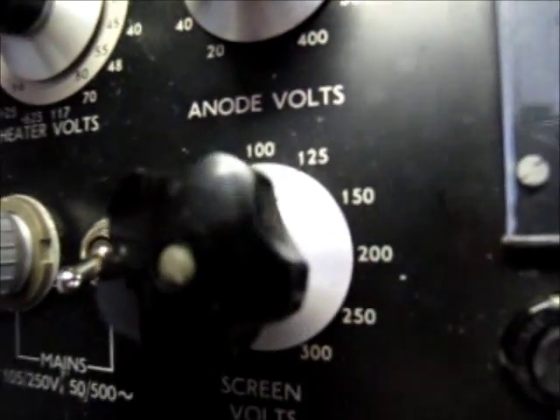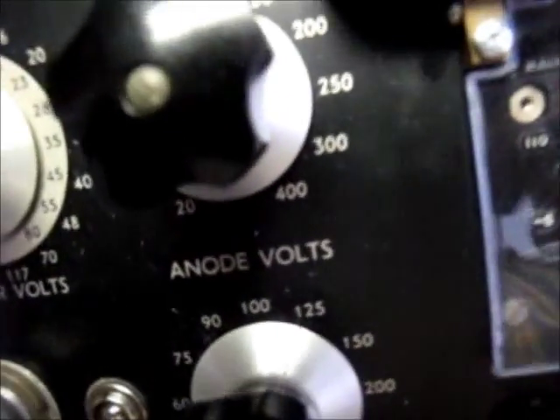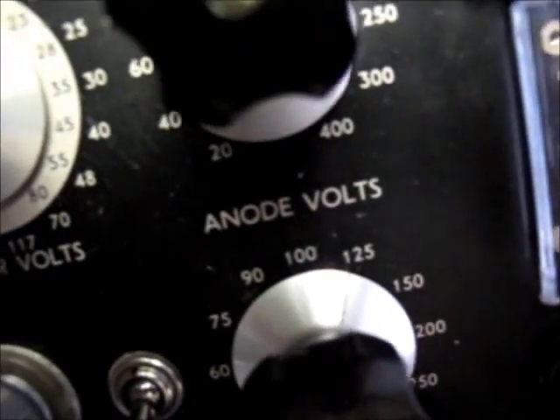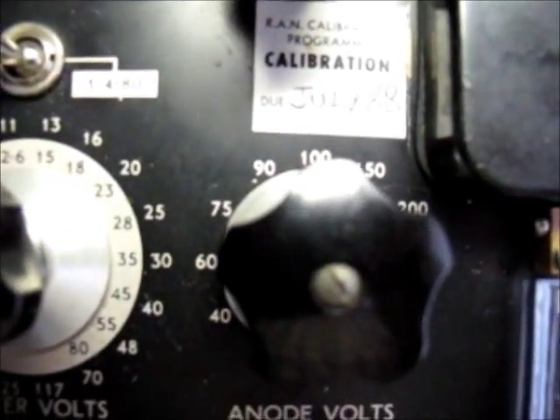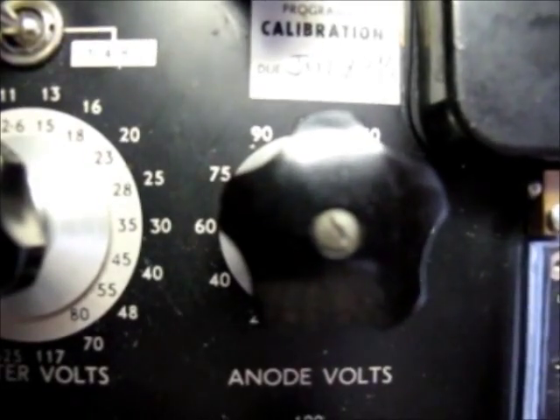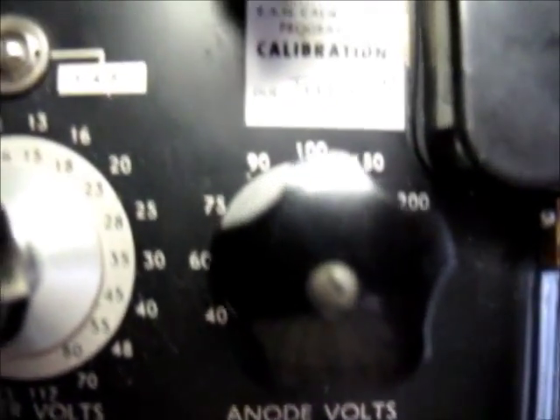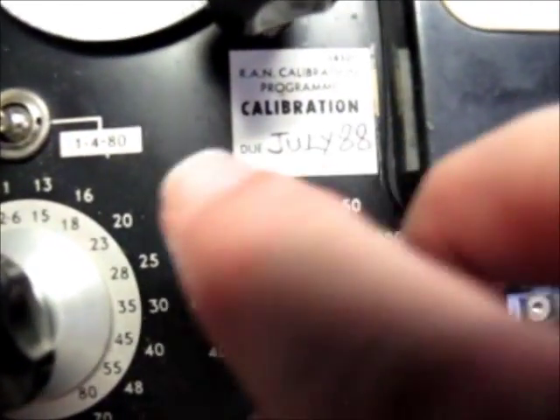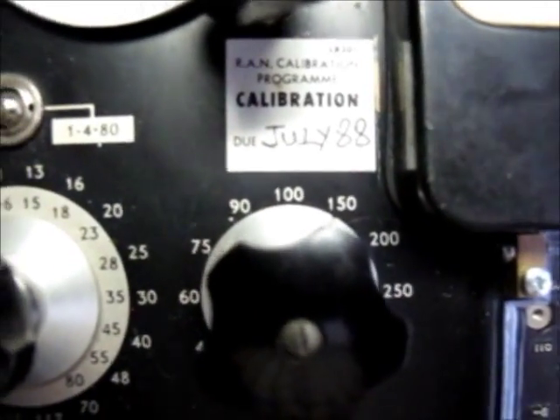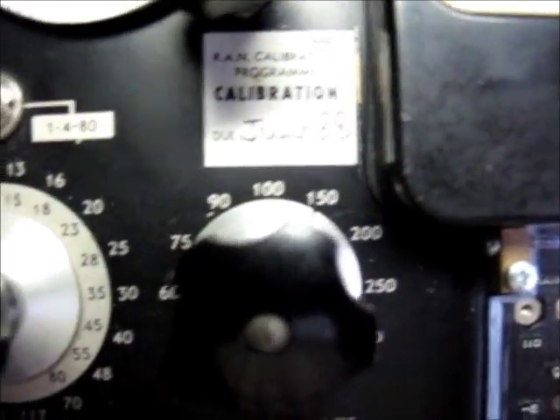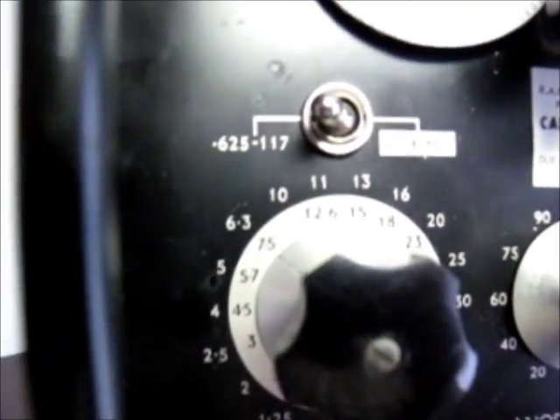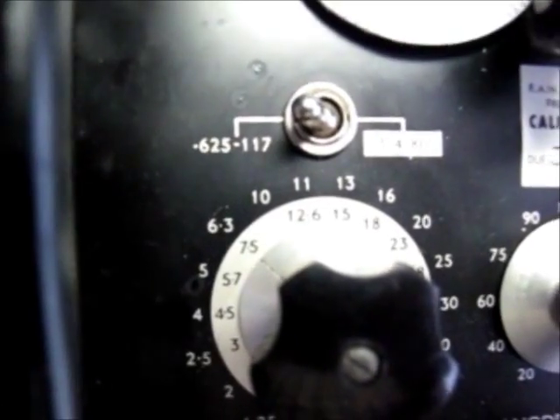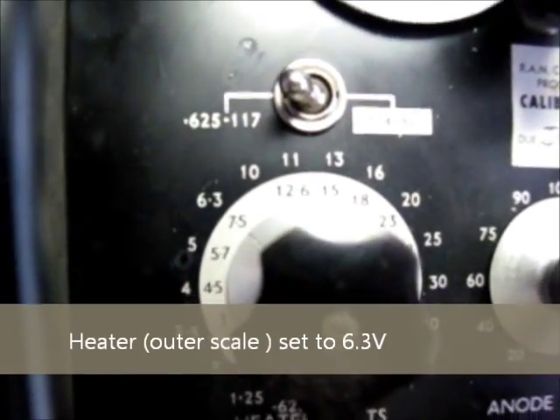Yeah, we're set for 120, I'm just trying to get the light on it so you can see the setting. There it goes, there you go, 125. Now I presume that this was probably meant to be about 150, 100 or 150 at least, so I'm going to put it to the 150 mark anyway, and we'll see how we go. The heaters are to the left of it, and the outer scale selected, which is 6.3 volts.